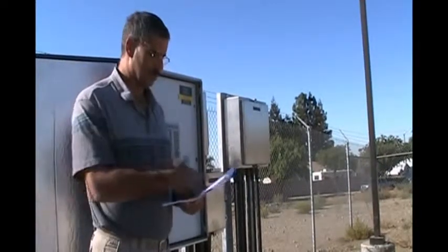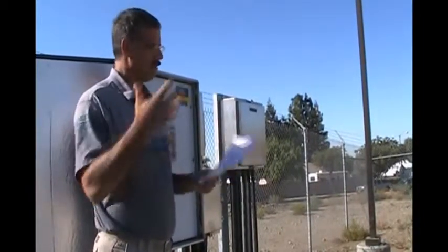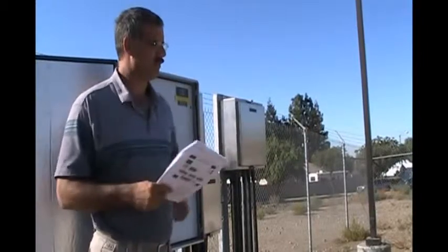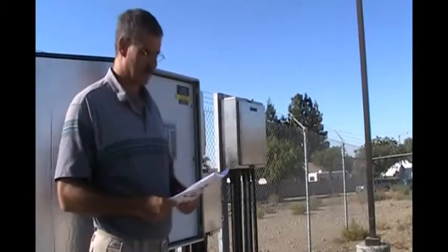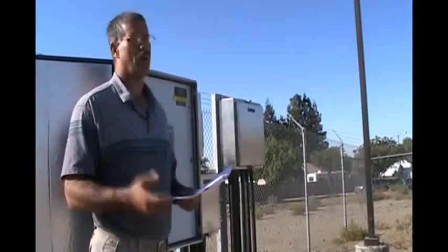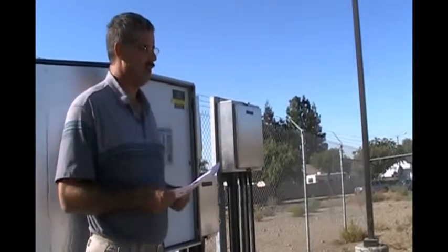In the auto mode, which is what you see on page 8, you have the ability to change the set point. So you would tap the green square, it'll bring up a dialog box, you type in whatever value you would like for the flow to currently be, and hit enter. That flow will not take effect right away.